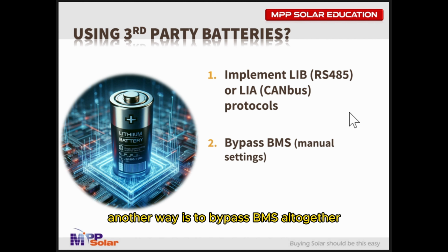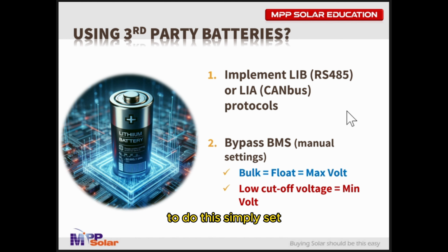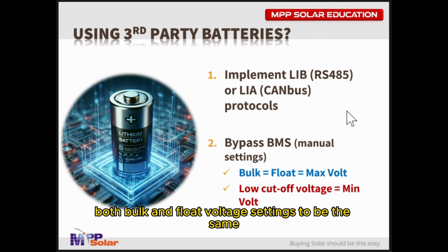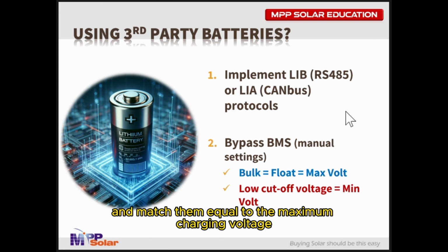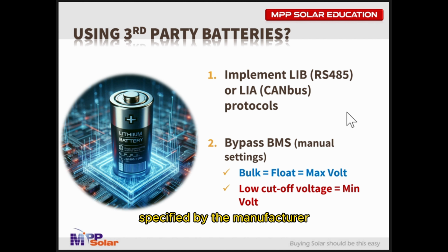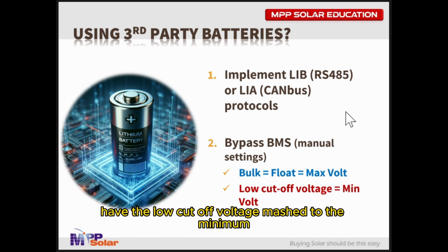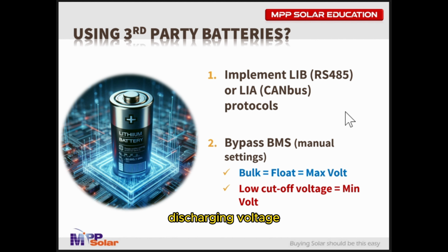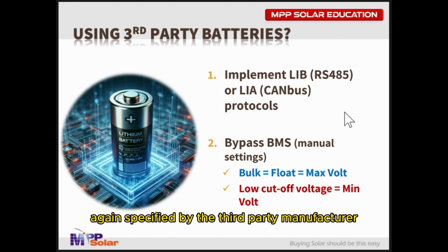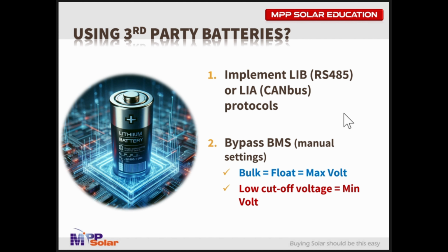Another way is to bypass BMS altogether and manually set up the inverter to match the charging requirement of your battery. To do this, simply set both bulk and float voltage settings to be the same and equal to the maximum charging voltage specified by the manufacturer, and also have the low cutoff voltage matched to the minimum discharging voltage, again specified by the third-party manufacturer, and that's all you have to do.